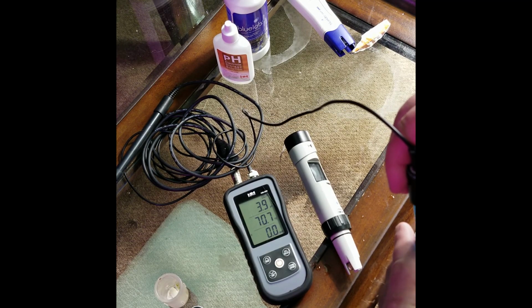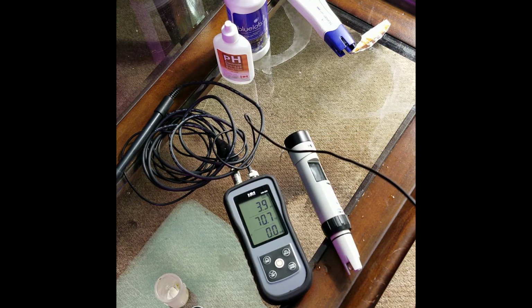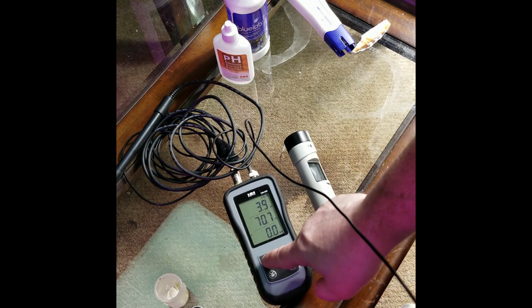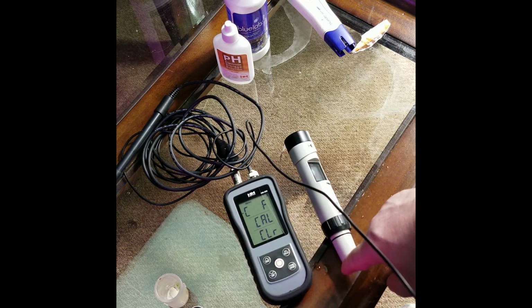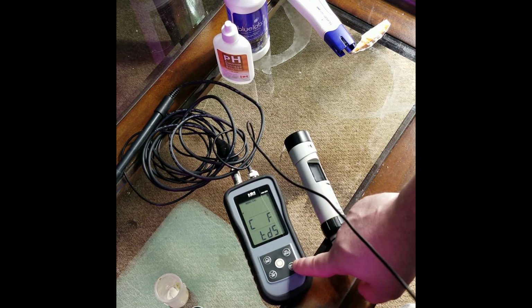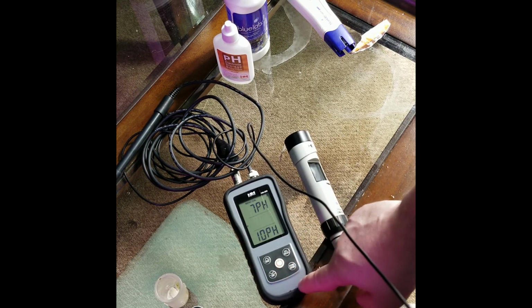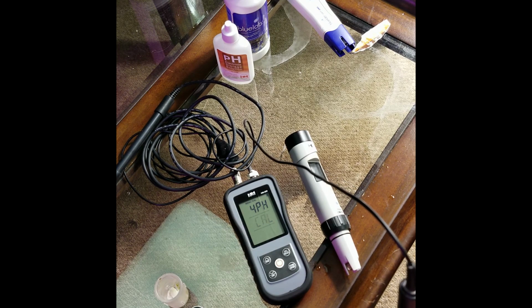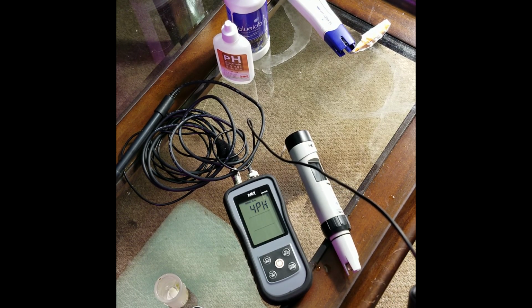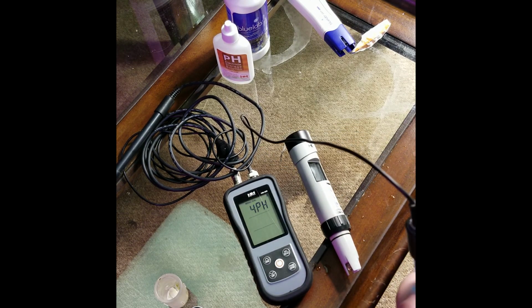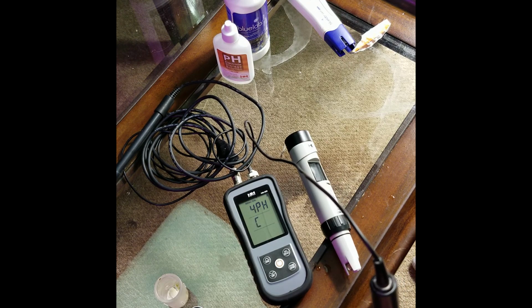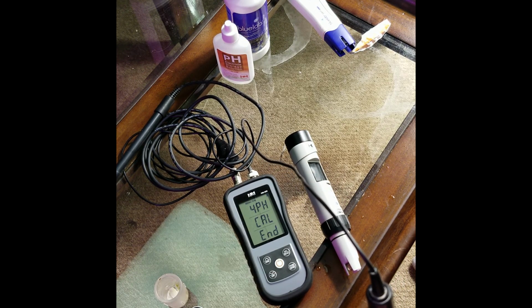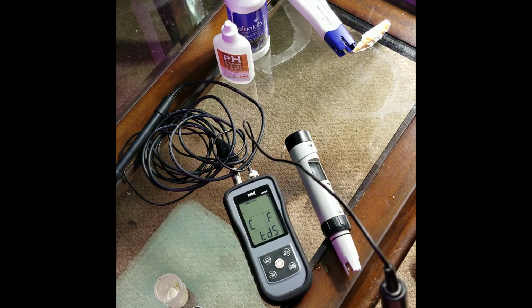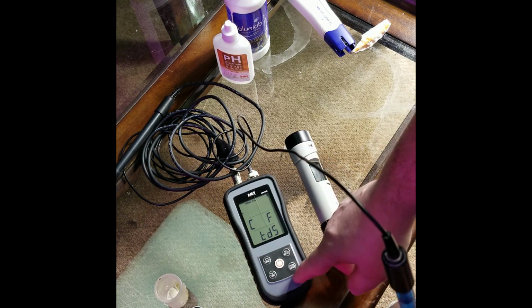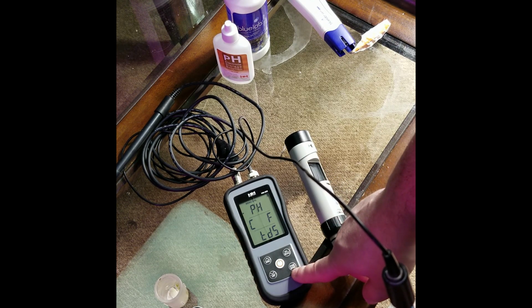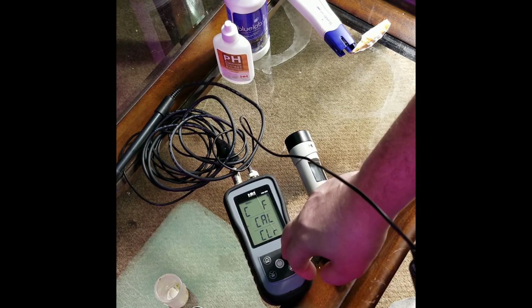So this one says 3.9, so we were at 7.1 and 3.9. So a little high and a little low. So same thing, we're going to press and hold menu, then we're going to go down one to calibration, hit enter, hit pH, and we're going to choose 4. And it's going to sit there and calibrate, making sure that the pH doesn't jump or fluctuate. This also has a pH of 10, so if you're reading high alkalinity situations, like, I don't know, you're making your own healthy water or something, you can get 10 solution and calibrate for 10. So there we are, this one calibrated. So once you have 7, then do 4, and then typically you're good to go.